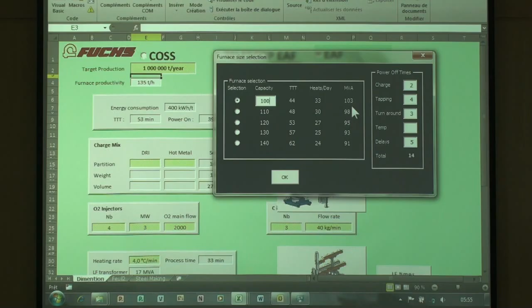And so you see, if I have 120 ton, it needs 53 tons an hour. 53 minutes tap to tap. So, in fact, maybe I could, let's say, decrease the furnace capacity, yeah? So let's put 100 ton. So it calculates here from 100 to 140 and to see, okay, 44 minutes still to be okay. 103 MVA for 100 ton capacity is a good figure. Huh? So I get here 100 ton, power on 30 minutes, 118 MVA.